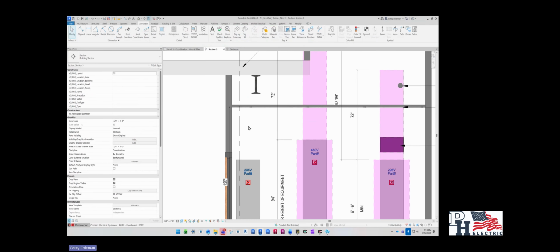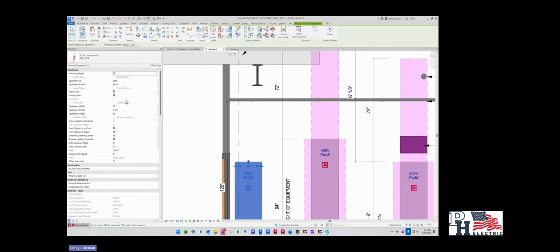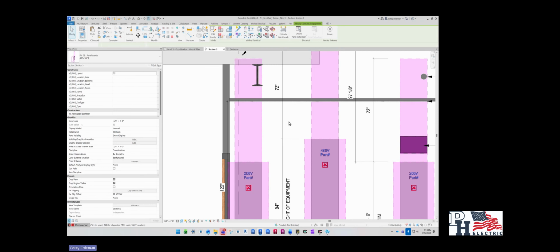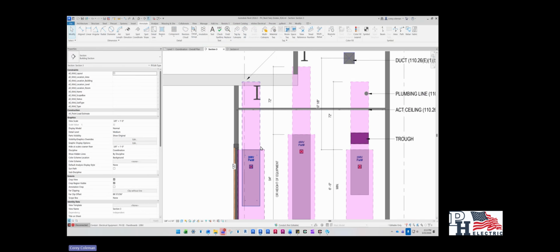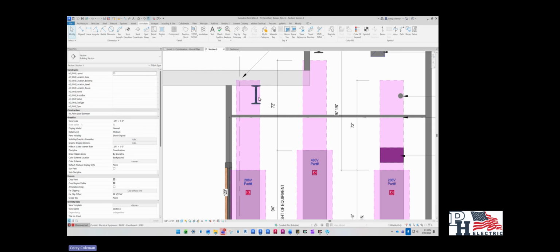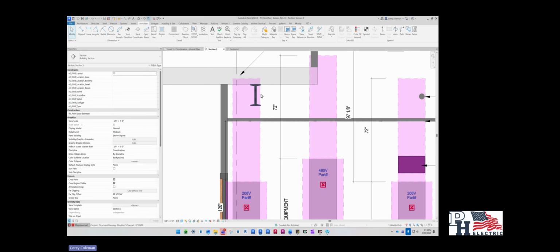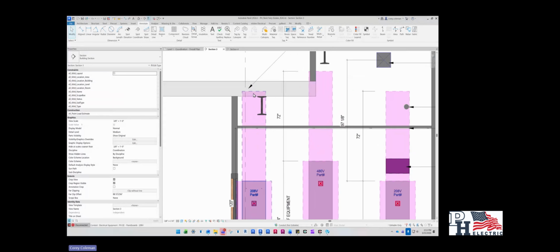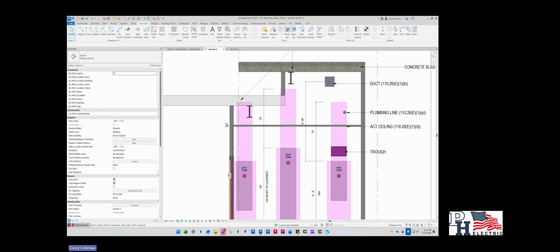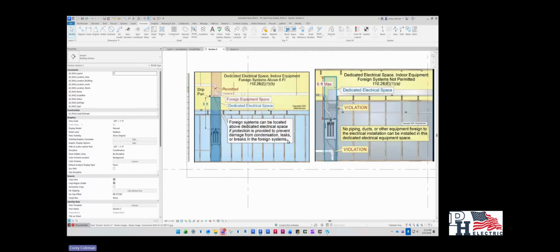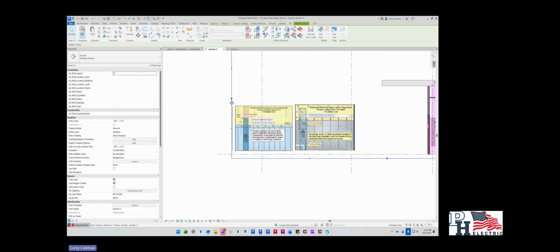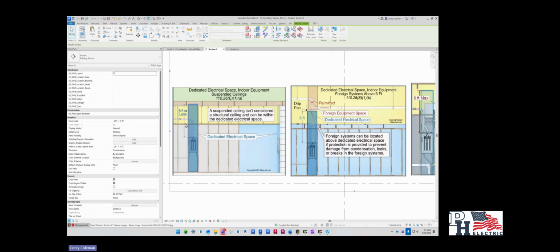This piece of beam here, generally for the most part, would be a code violation with your panel being underneath it, because it intrudes in that 6 feet space. Most inspectors don't seem to have an issue with it, but just be aware that they could call you out on it, because the code calls for the structural ceiling, not an actual structural element.